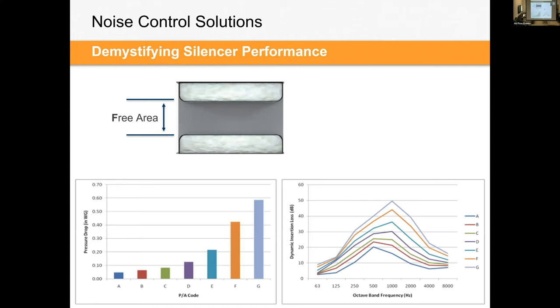What is the purpose of this? Well, silencers provide two things primarily, insertion loss and pressure drop. Insertion loss is a good thing. You want to take out sound. Pressure drop is a bad thing. You're obstructing the flow. You're creating back pressure.